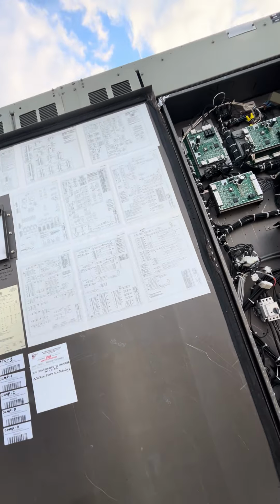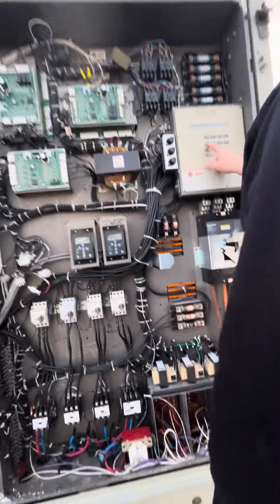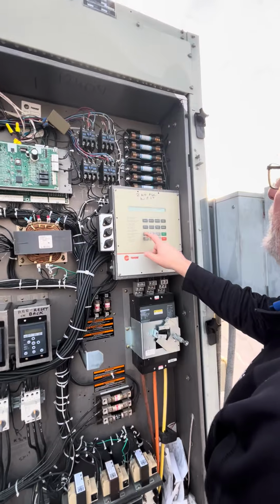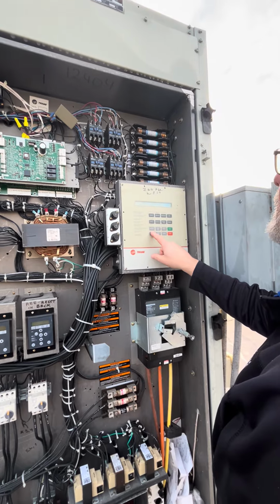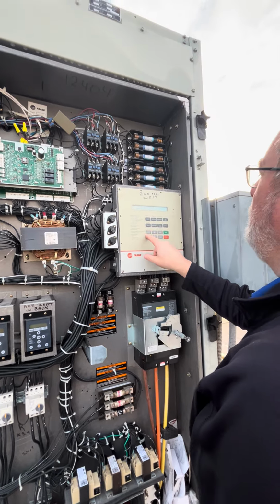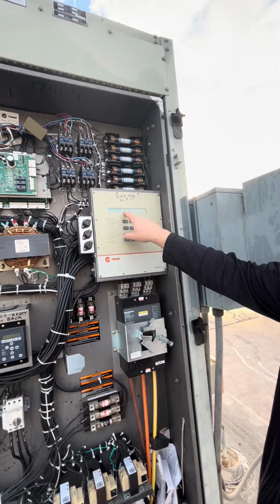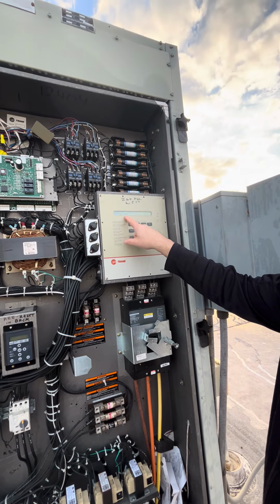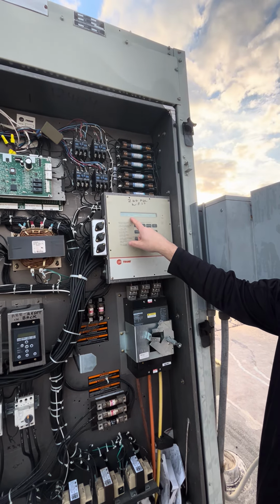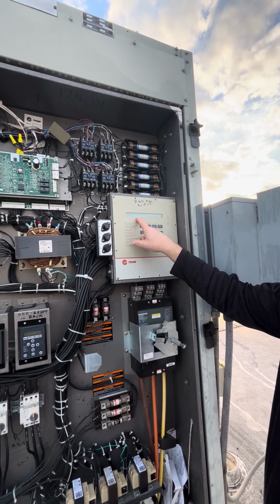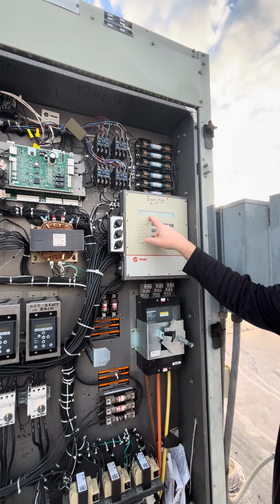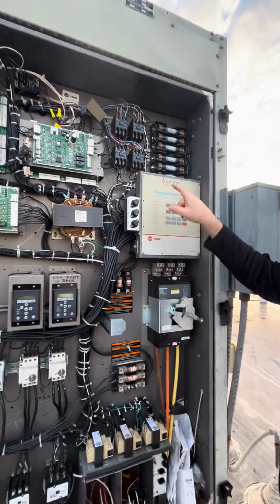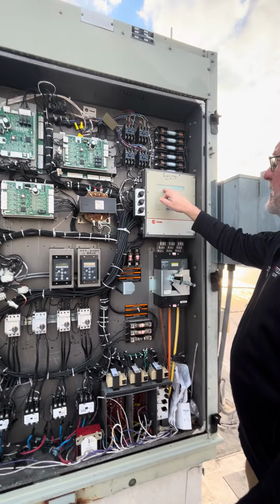Okay. And that is under setup, under general. Right there. Demand limit definition. Cooling is 100%. We're set up for 100% lockout. The options are 0, 50, or 100. You can't say give me 25% of your cooling. It's 0, 50, or 100. So we set that to 100.